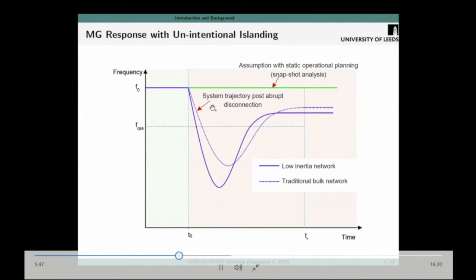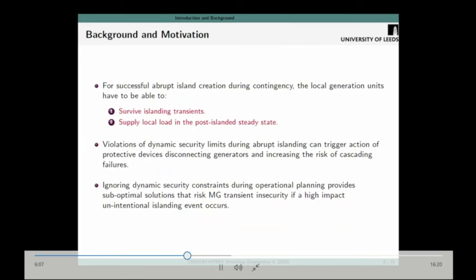And as such, we observe that the frequency response of low inertia networks after an islanding event has a higher risk of violating the different security limits that are available for the microgrid operation. As such, for the successful creation of an abrupt island after a contingency, the microgrid has to, one, be able to survive the islanding constraints and, as well, continue to serve the load in the post-islanded state. If we have violations in the dynamic security limits, we risk the operation of the different protective devices of the generators, leading to their disconnection from the network and increasing the risk of cascading failures.